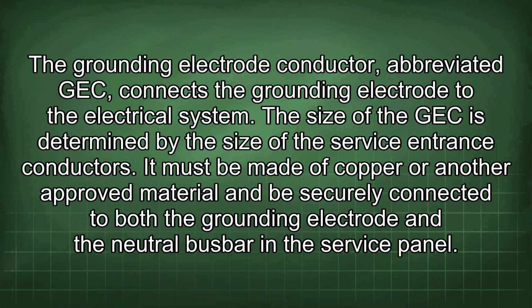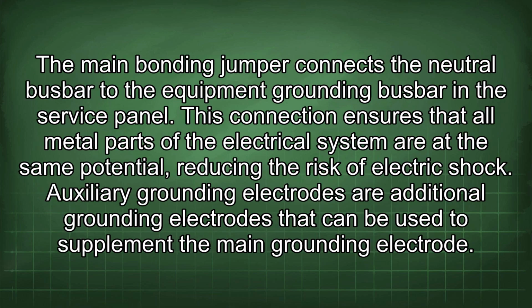It must be made of copper or another approved material and be securely connected to both the grounding electrode and the neutral busbar in the service panel. The main bonding jumper connects the neutral busbar to the equipment grounding busbar in the service panel. This connection ensures that all metal parts of the electrical system are at the same potential, reducing the risk of electric shock. Auxiliary grounding electrodes are additional grounding electrodes that can be used to supplement the main grounding electrode.